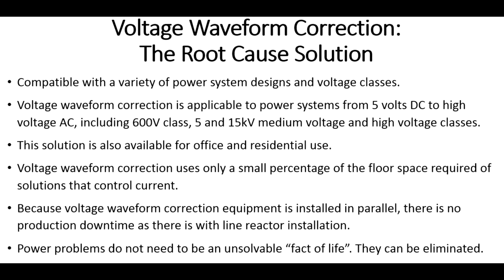The line reactors we talked about earlier, as you install them, you have to shut all of the equipment down. To install voltage correction, everything can operate, because it connects in parallel, just like another piece of equipment. It just ties into a 30 amp 3-pole disconnect, and you hook your 3 phases up and ground, and as you turn the disconnect on, your power is immediately being cleaned up. You do not have to believe power quality issues are business as usual. They now can be eliminated.